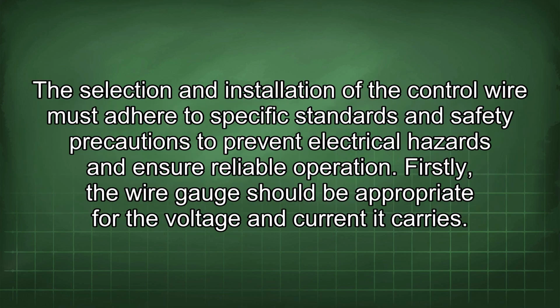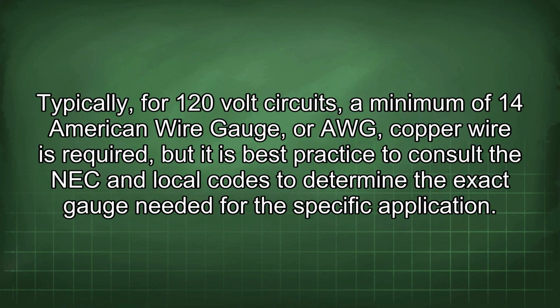The selection and installation of the control wire must adhere to specific standards and safety precautions to prevent electrical hazards and ensure reliable operation. Firstly, the wire gauge should be appropriate for the voltage and current it carries. Typically, for 120-volt circuits, a minimum of 14 American Wire Gauge, or AWG, copper wire is required, but it is best practice to consult the NEC and local codes to determine the exact gauge needed for the specific application.